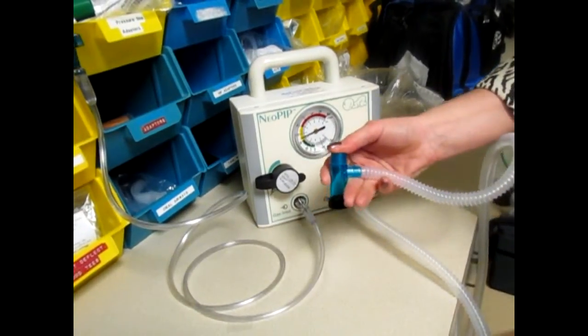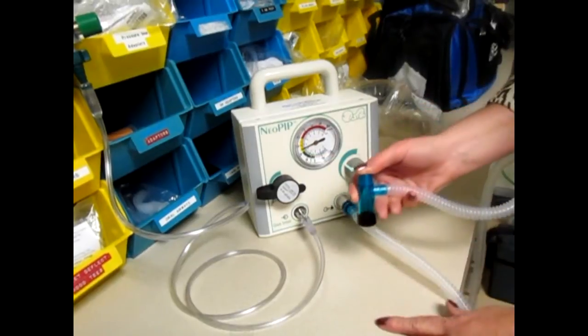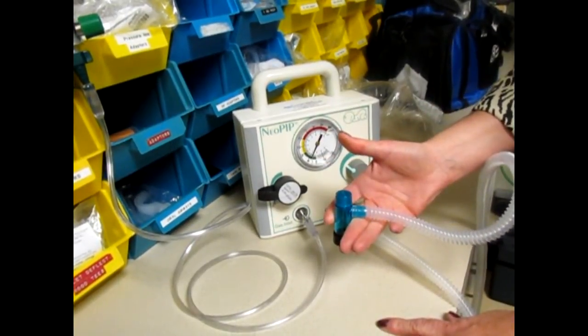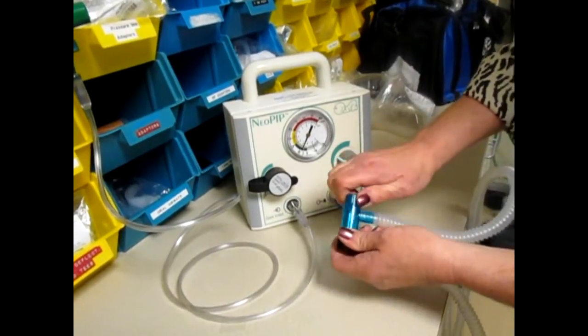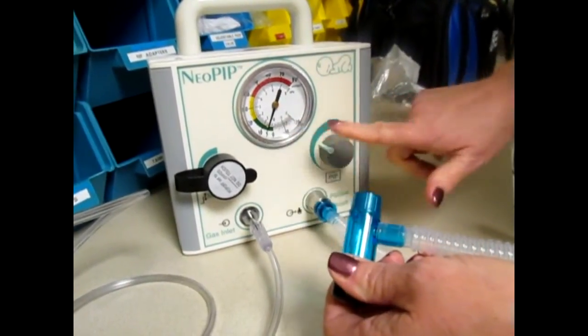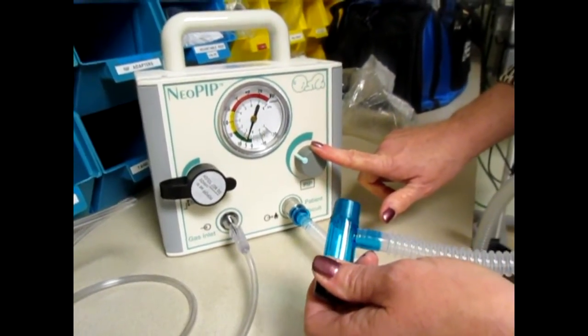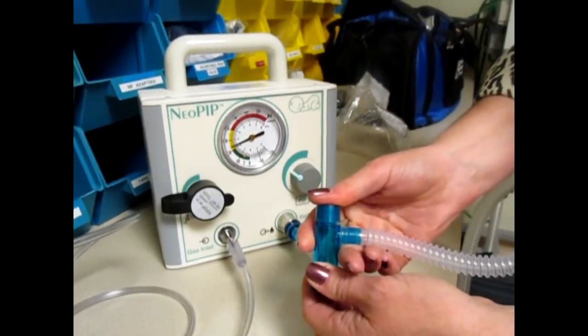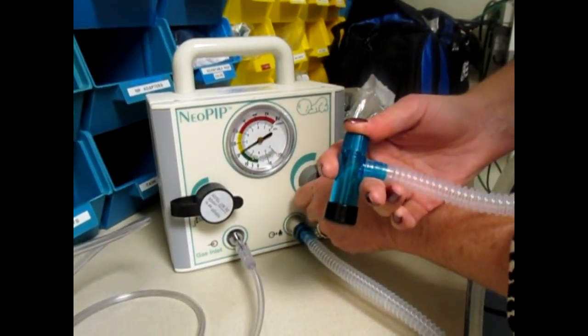Any time they have their thumb occluding this, it's giving an inhaled breath, inspiratory pressure of what you have set on the manometer. Every time they let go, they're exhaling for the patient and they're exhaling down to the PEEP that's set. So again, as I turn this, I can manipulate my PIP. This knob manipulates the PIP. Do you understand the 20 over 5? 20 over 5, and it looks like I need to come down a little bit on that with that leak.